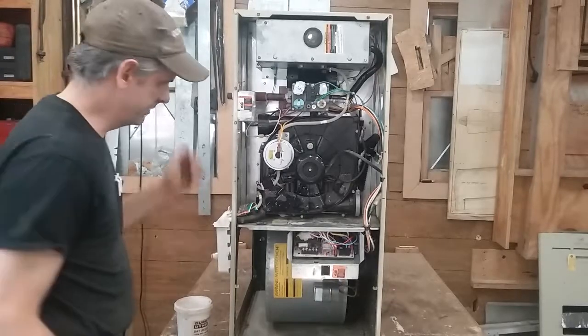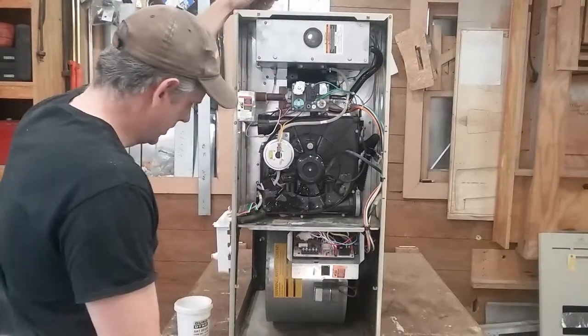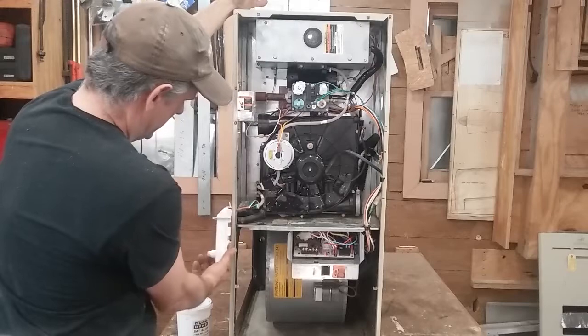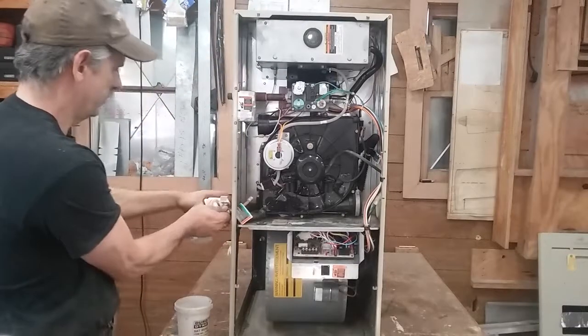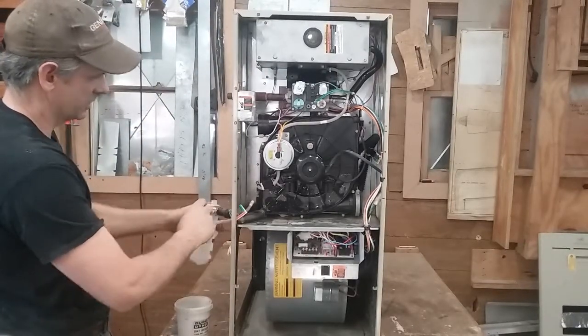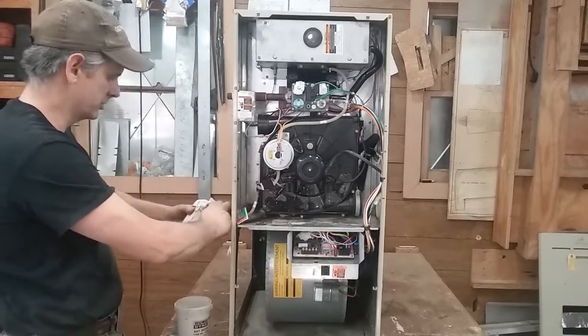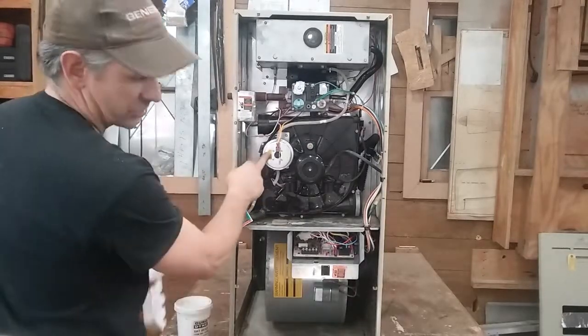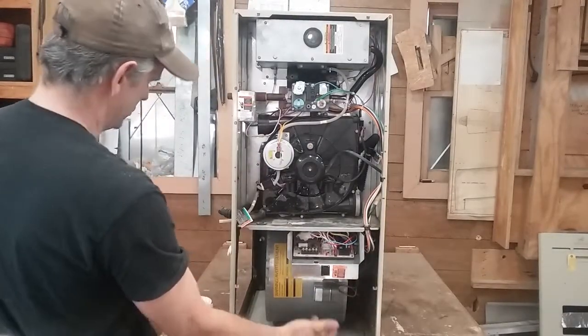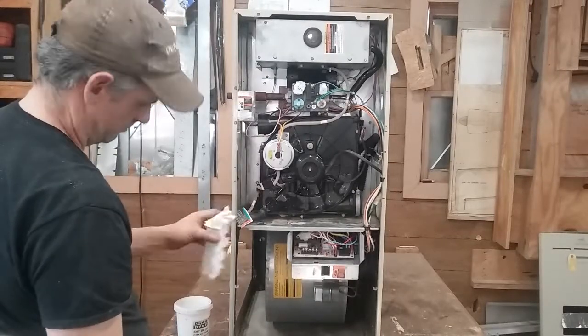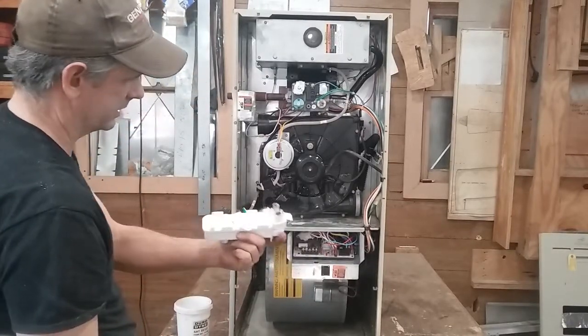Okay, so here's some common everyday failures. Number one: this here is the drain trap. If the drain trap gets plugged up, or the drain line or the drain hoses get plugged up, the pressure switch will not close, and you'll get a pressure switch error. They kind of almost all look like this.